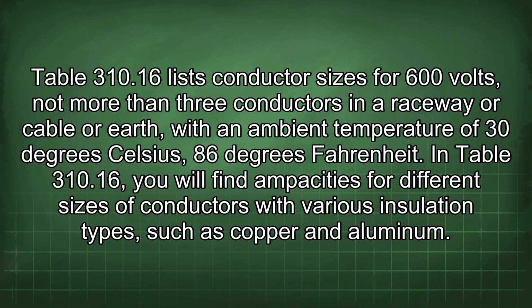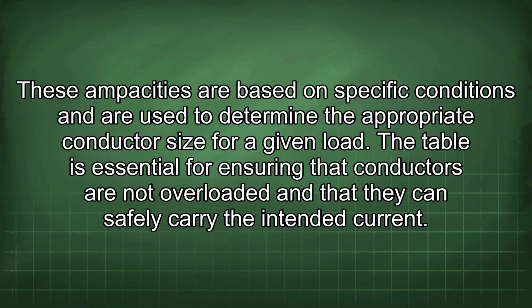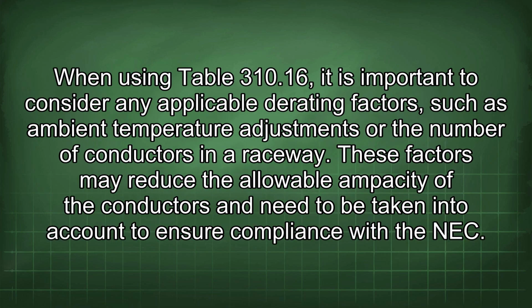In Table 310.16, you will find ampacities for different sizes of conductors with various insulation types, such as copper and aluminum. These ampacities are based on specific conditions and are used to determine the appropriate conductor size for a given load. The table is essential for ensuring that conductors are not overloaded and that they can safely carry the intended current. When using Table 310.16, it is important to consider any applicable derating factors such as ambient temperature adjustments or the number of conductors in a raceway.